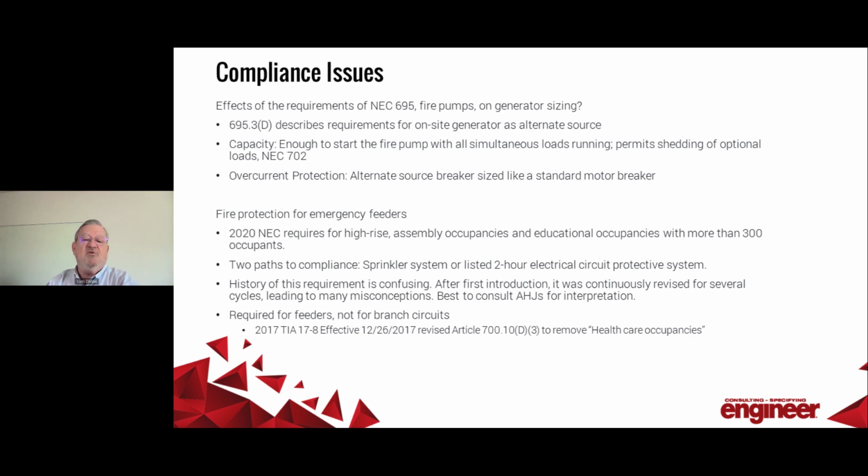Healthcare occupancies used to be on the list of occupancies in the 2017 NEC, but that requirement was amended out in 2017. NFPA 99, the Healthcare Facilities Code, started exempting healthcare from the requirements for fire protected feeders with the 2015 edition.